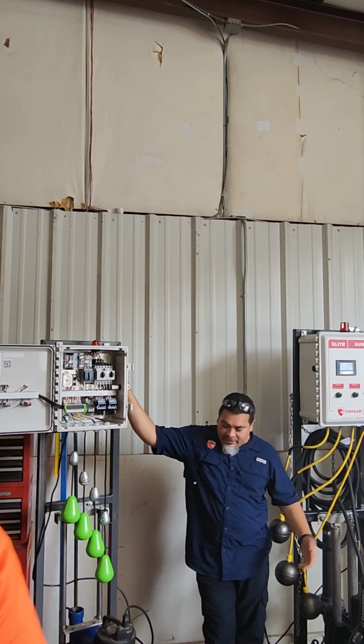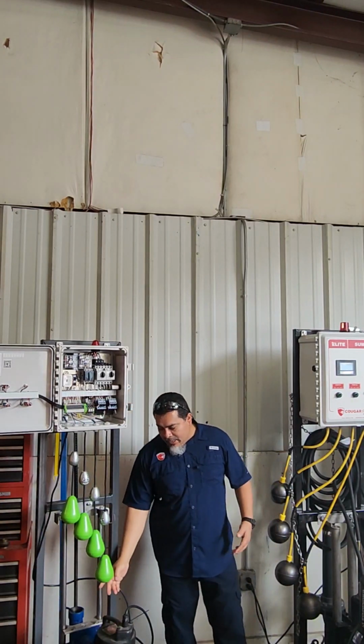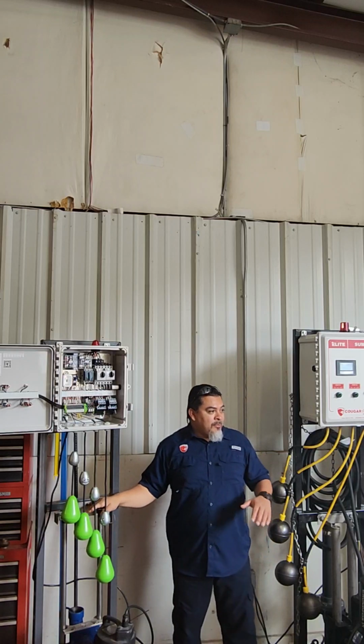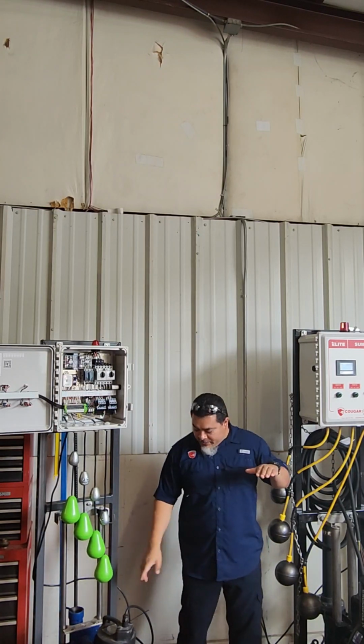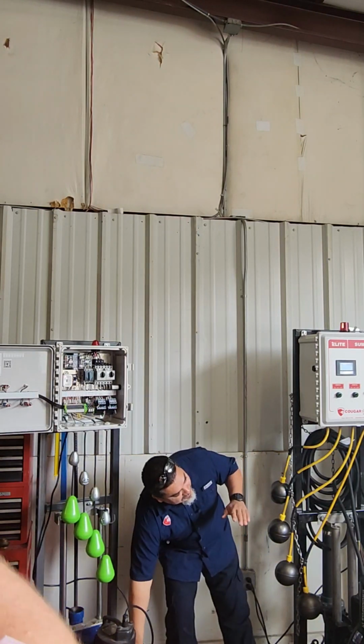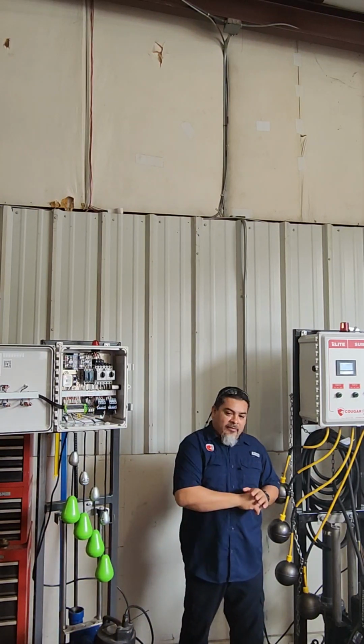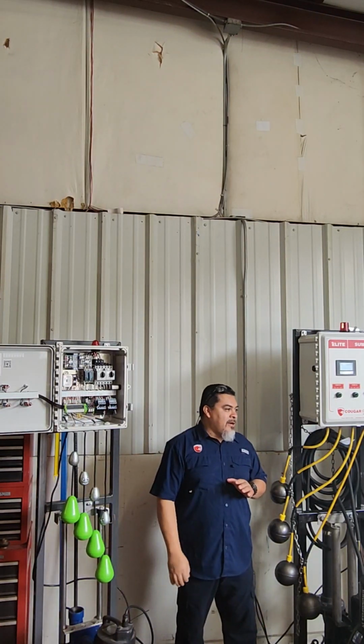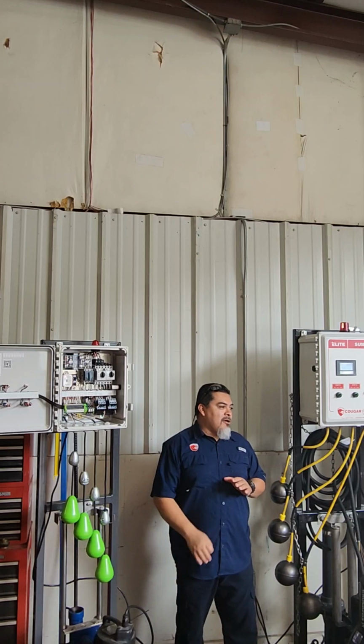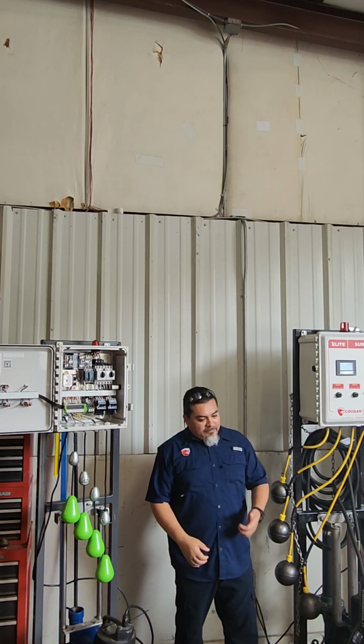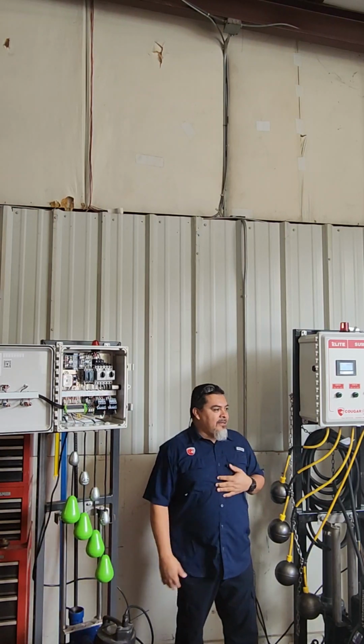The best way to always check and see if the pump is pumping, you pull it up. And you bring it just above the water where you can see the discharge side, but it's still on the water. Turn it on, and you'll see it splash water against the pump wall. Because I get a lot of those calls, hey, my pump ain't pumping. Go pull it up, see it, okay, it does pump.